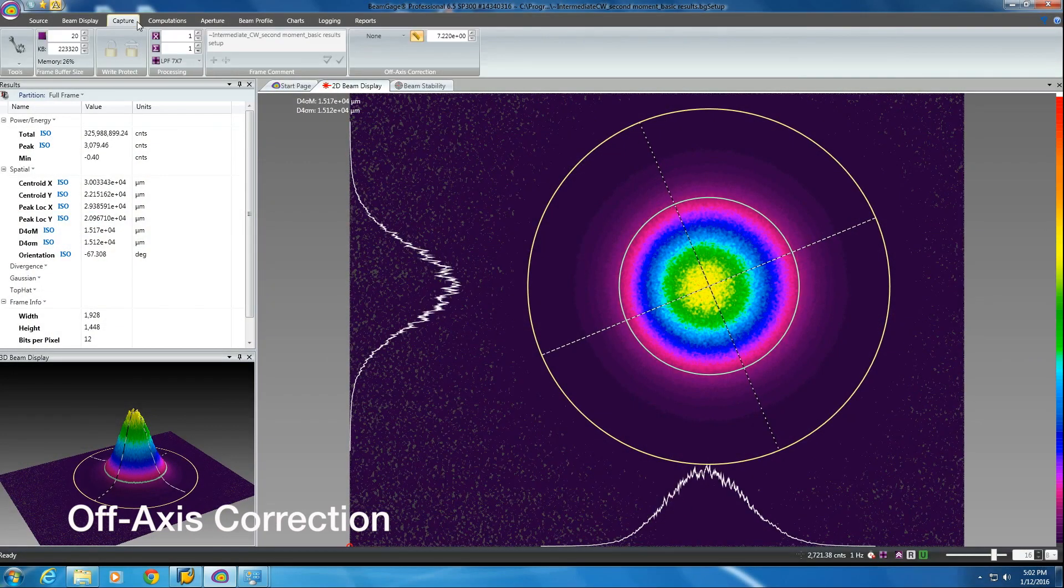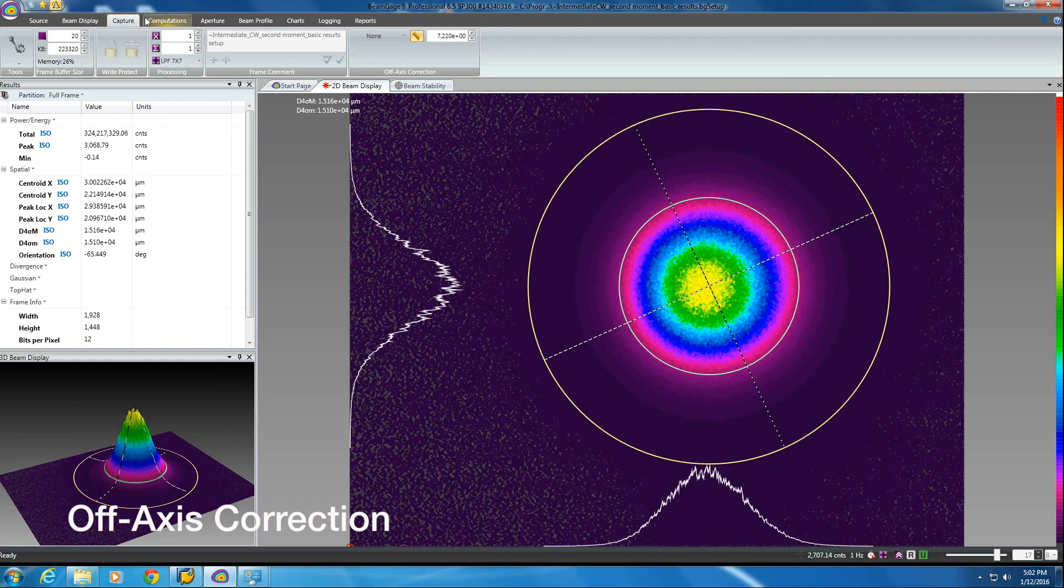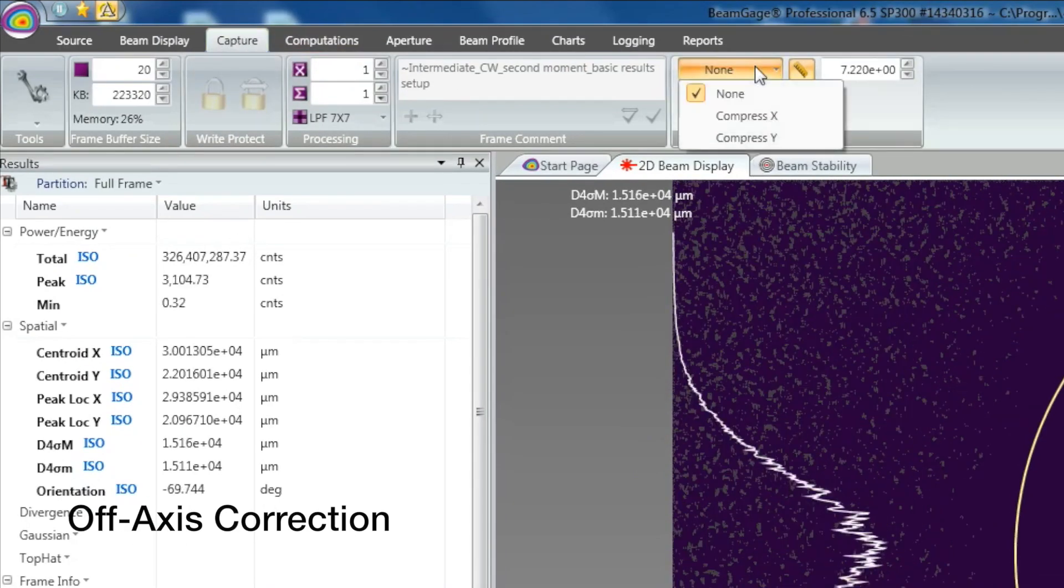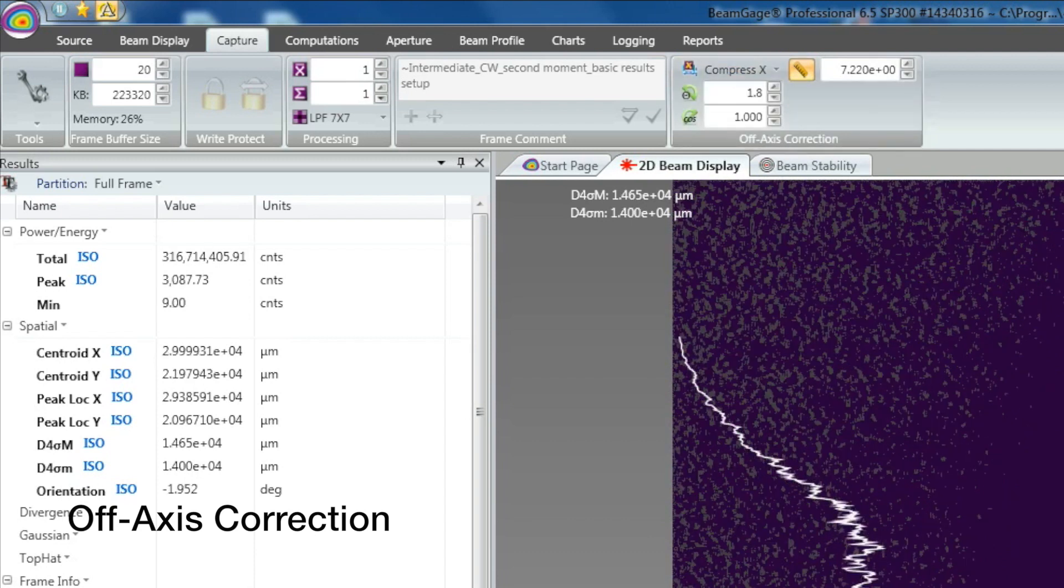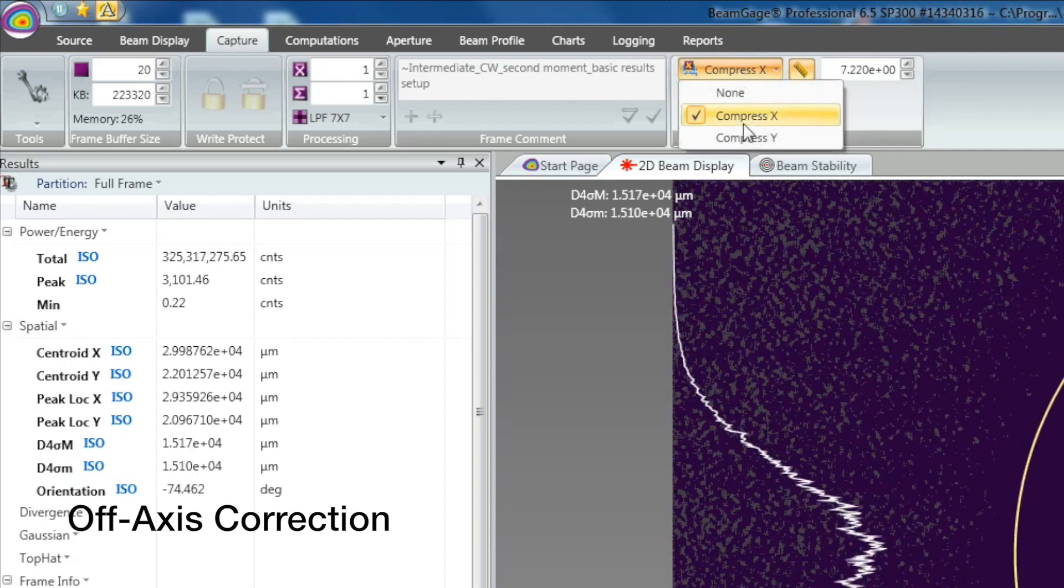Off-axis correction is available in BeamGage Professional. It allows the user to correct for beam aspect ratio distortion when the beam under test is compressed in one axial direction.